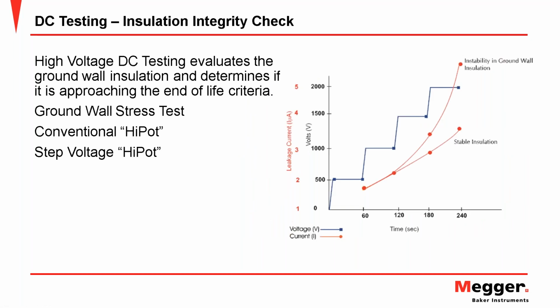Now, moving into high voltage testing, we're basically leveraging that same type of test that we did for the insulation resistance at nominal values and slowly increasing that voltage level to the stress level that it's going to have to endure during brief periods of time during its life. Namely, when we either start or stop the motor, anytime there's contact making and breaking, there's a potential for an inductive kick voltage or an operational stress that could be very high. And so we want to make sure that the insulation is capable of handling that stress.